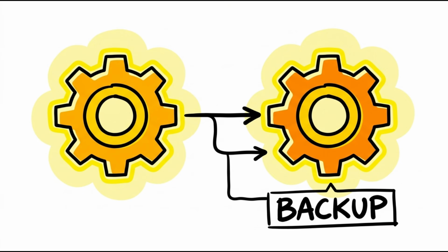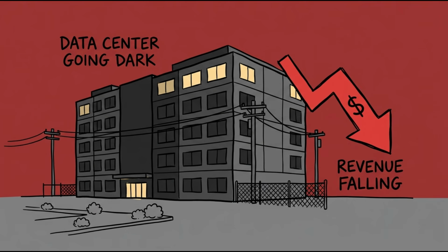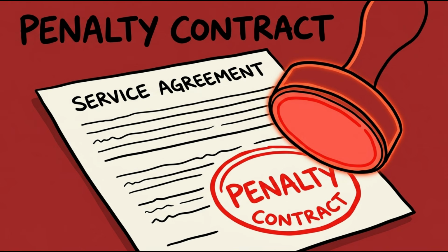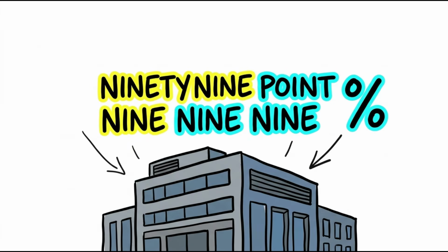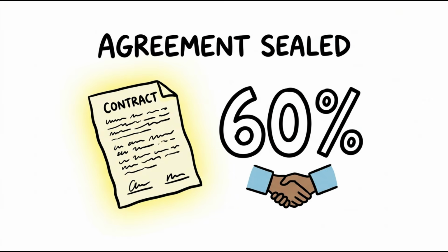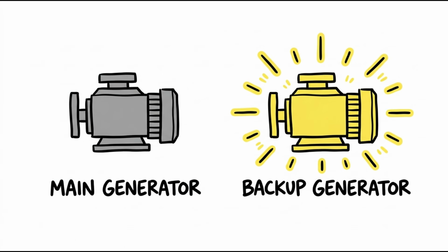Then there's a cost that has nothing to do with computers at all: redundancy. A data center that goes offline doesn't just lose revenue for the hours it's down, it can trigger contractual penalties, because customers pay for uptime guarantees, often expressed as 5 nines, meaning the facility is contractually promised to be operational 99.999% of the time. Meeting that promise means duplicating almost everything that matters: backup generators, redundant power feeds from separate points on the grid, backup cooling systems.